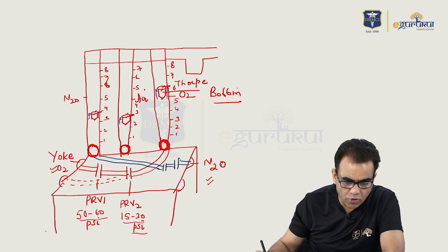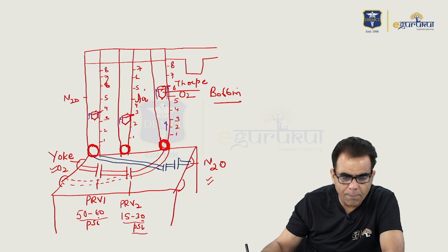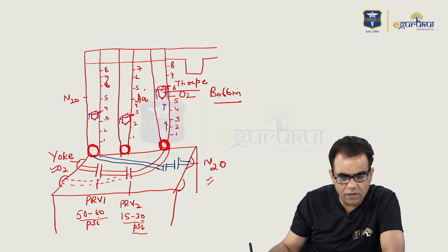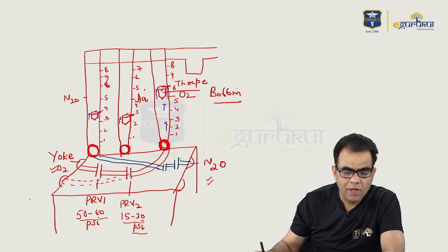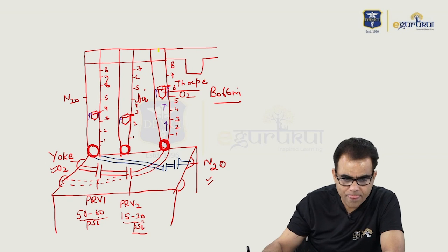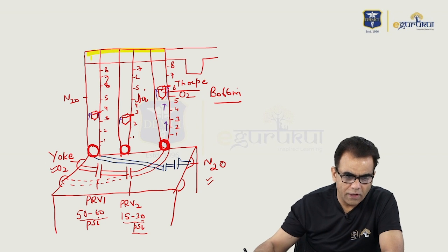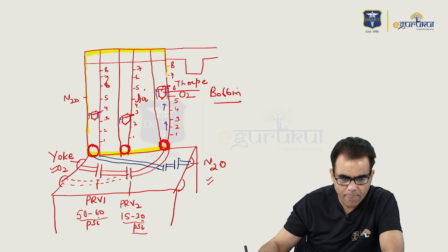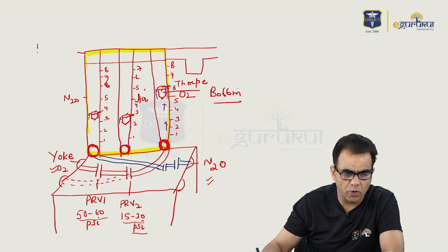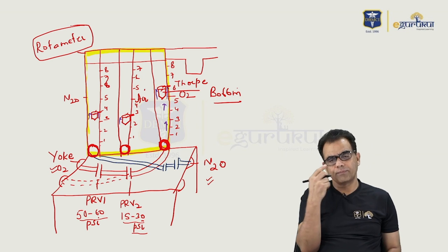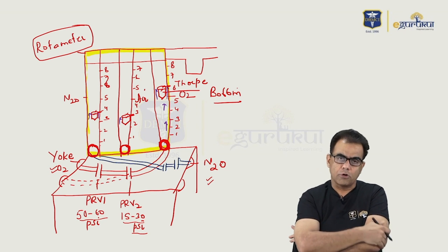If you want to increase the flow, you rotate the knob, more gas will come, and the bobbin will go up. If you want to reduce the flow, rotate the knob the other way and the bobbin will come down — that is how you determine the flow rate. This whole unit containing different flow meter tubes and flow control knobs is called the rotameter. It is called rotameter because it has a rotating bobbin in it.